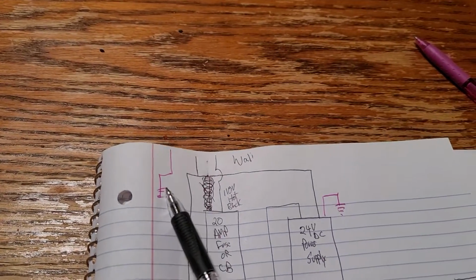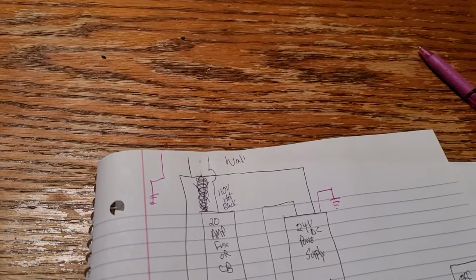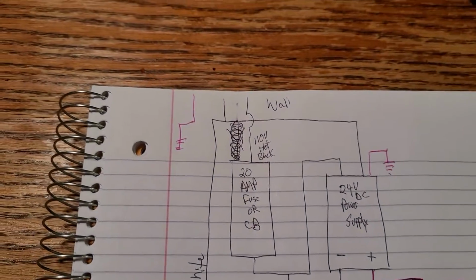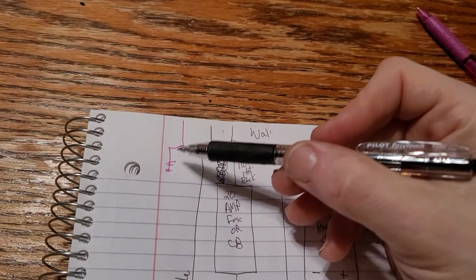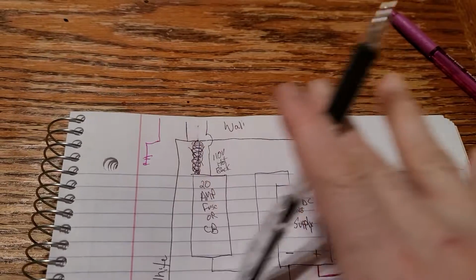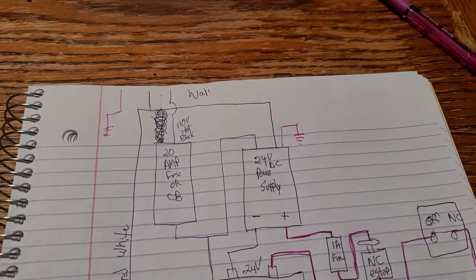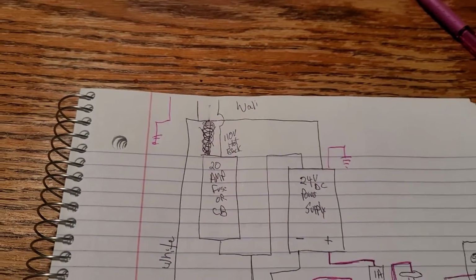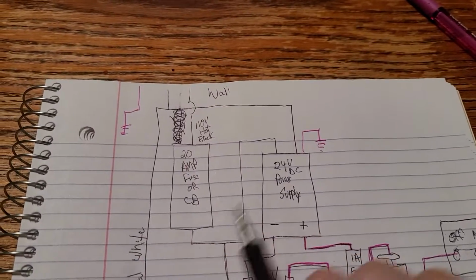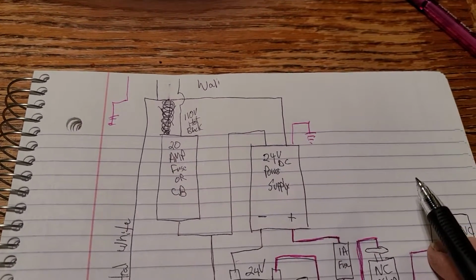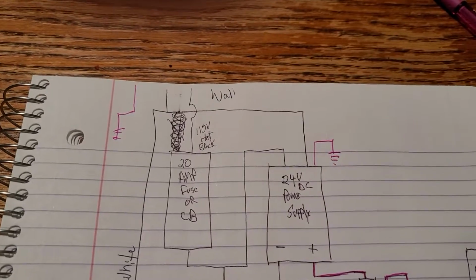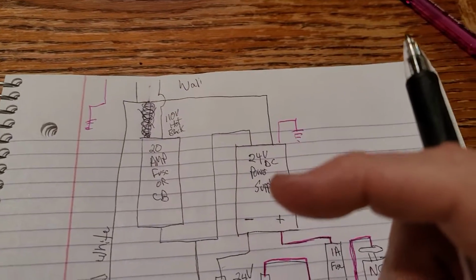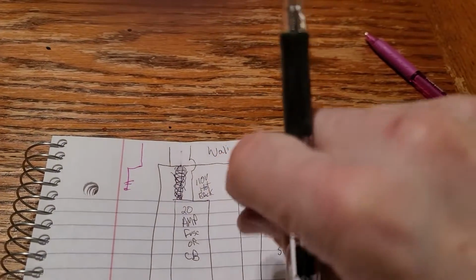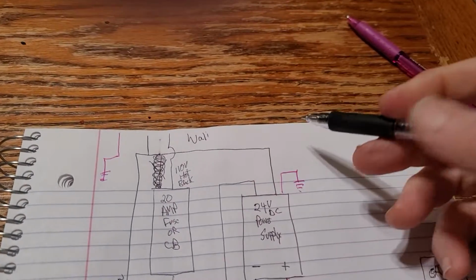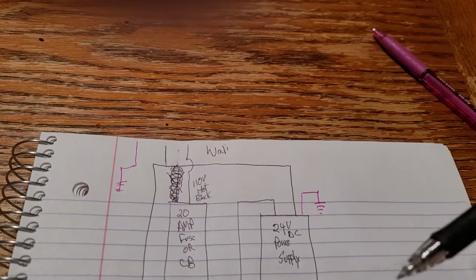So the ground in your box, you're going to run to the lug that grounds pretty much everything that gets connected inside there, right? And what I do is I connect that back plane, that steel back in my box, to ground. And then when the DIN rail is screwed to that steel back, now the DIN rail itself is grounded. And then you can buy green DIN terminals that, when you screw them down to the DIN rail, then those contacts themselves are grounded.